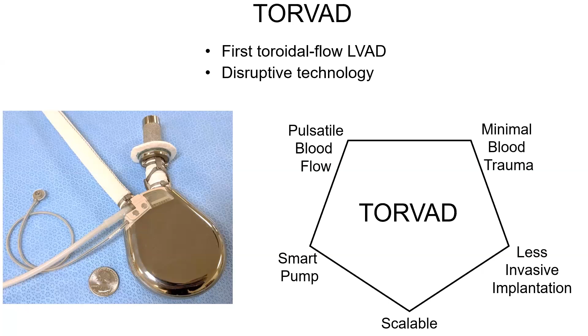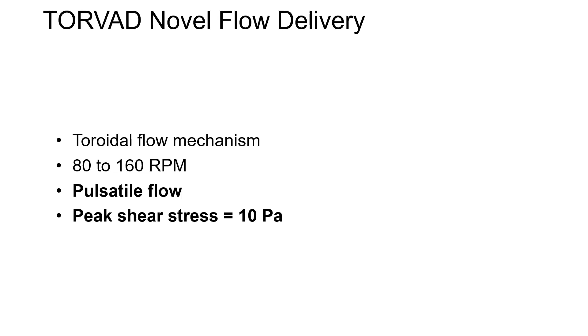Flow delivery is via a totally different mechanism with the TORVAD, a toroidal flow mechanism. Rather than spinning at thousands of revolutions per minute, like the previous generation devices, it spins at 80 to 160 revolutions per minute, which is comparable to the native heart rate of 80 to 160. Again, it generates pulsatile flow, and this device was designed to generate low shear stress. The peak shear stress that it generates, not the mean shear stress, is 10 pascals. You can compare this to devices that generate orders of magnitude higher shear stress than this. How does it work?